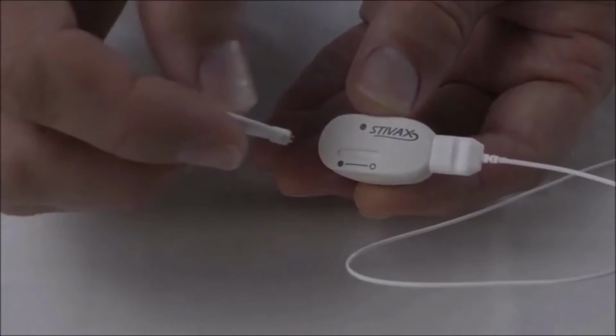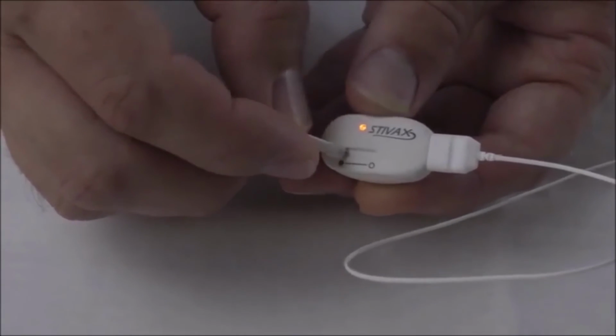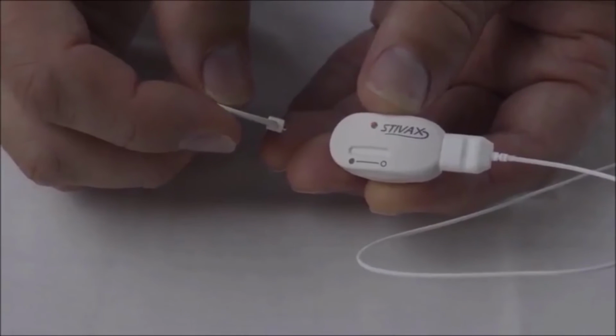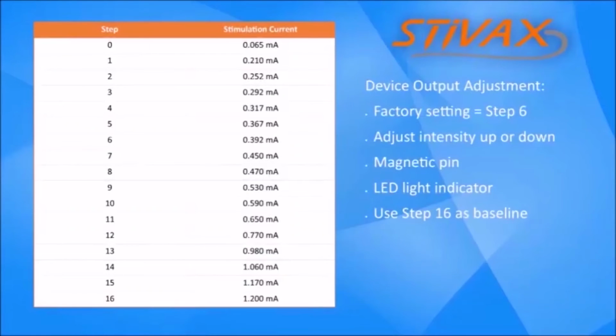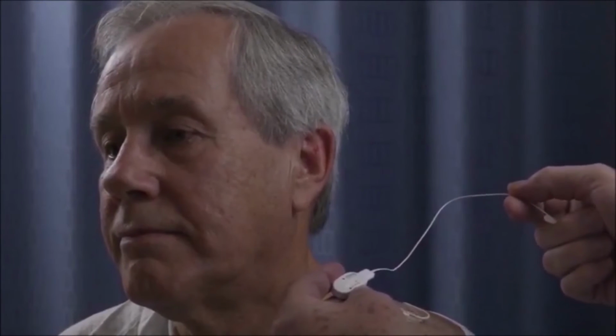If level is unknown, increase the intensity level until the LED blinks 4 times. This indicates the device has reached level 16, its highest setting. Likewise, if your office has a Stivax current multimeter, you can also use that to determine the device's current stimulation setting. The Stivax device allows for setting the intensity in the range of step 0 to 16. The default factory setting is set to step 6. Secure the stimulator into the clip to prevent the weight of the device from interfering with the installation of the needle array. You'll hear a click when the device has been secured in the clip.